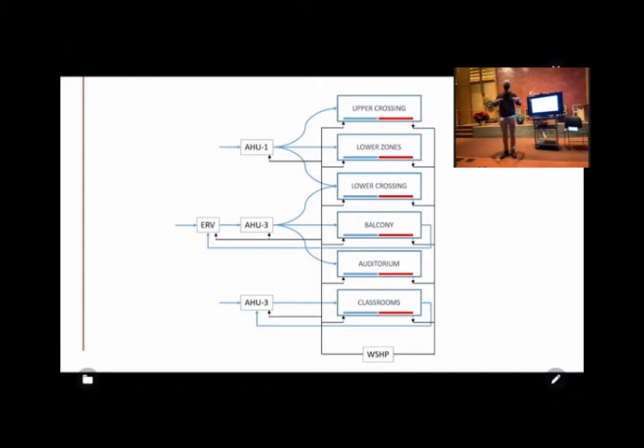So we put in a thermal storage buffer tank. We ran the radiators off the buffer tank, and when the buffer tank started to get cold, kick on the heat pump, heat up the buffer tank, all done. So we were begging to have a tank in here. And the manufacturer's rep for the water source heat pump said, no, you don't need it. You've got plenty of volume in the system. You're not going to need it.